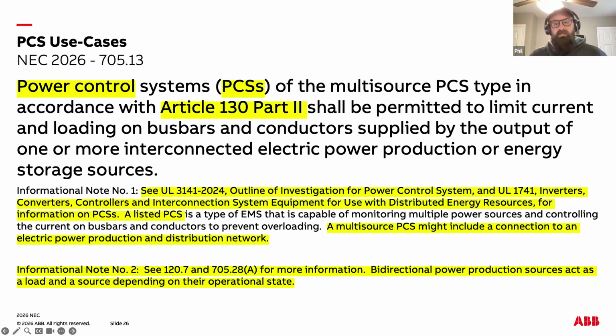In the highlighted text, you can also see the updated listing requirements, which now reference UL 3141 and UL 1741. One important point that remains consistent between the 23 and 26 versions is the core permission. A PCS is allowed to limit the current and loading on bus bars and conductors. That wording is deliberate. It means the PCS can manage both sources, like PV or ESS, and loads, such as EV chargers, giving designers a flexible tool for keeping the electrical system within safe operating limits without automatically triggering service upgrades.